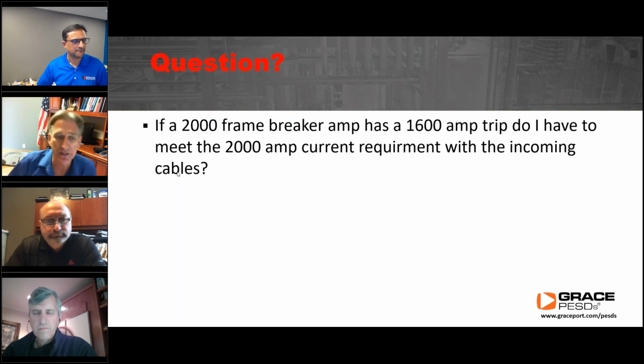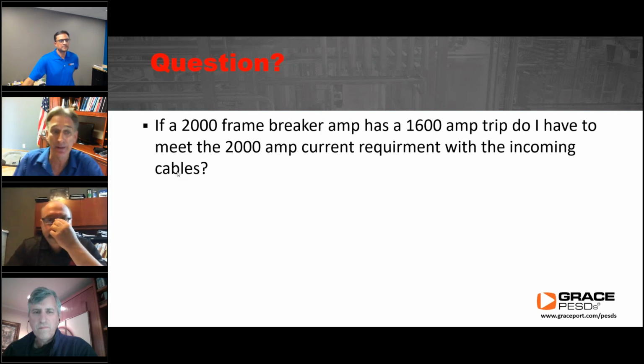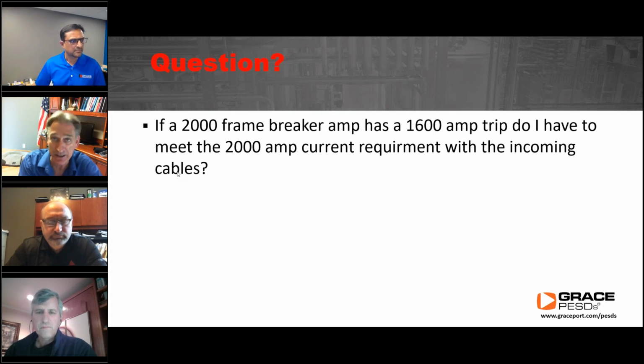But if it has an external means for adjusting the current setting, long time pickup setting, not meeting the requirements of 240.6C, it shall be the maximum setting possible. Therefore, if this question about the 2000 amp frame breaker, it meets B and not C, then the conductors installed would have to be rated up to 2000 amps. All right, so what does C say?